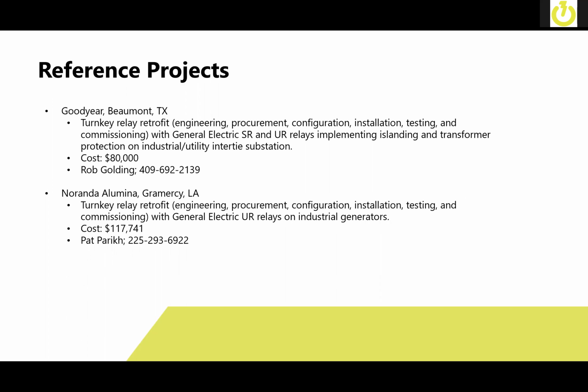We've done some jobs over in Beaumont, Texas. Again, turnkey relay retrofit, General Electric SR and UR relays, which are different platforms within the GE relaying system. Implementing islanding during faults. They have a generating system where they had frequent faults on the utility, and they wanted to be able to just island from them because the generator had the capability to fully handle the plant load. And they also wanted to upgrade the transformer protection on the industrial/utility intertie substation. Noranda Alumina down in Gramercy, Louisiana, wanted to do a turnkey relay retrofit again with GE UR relays on their generators.